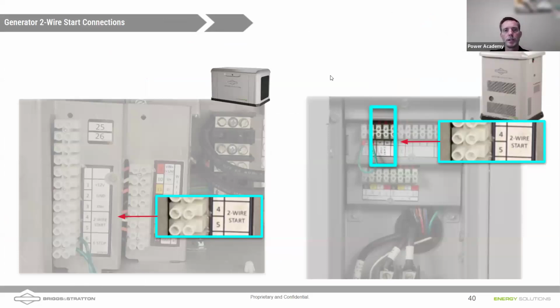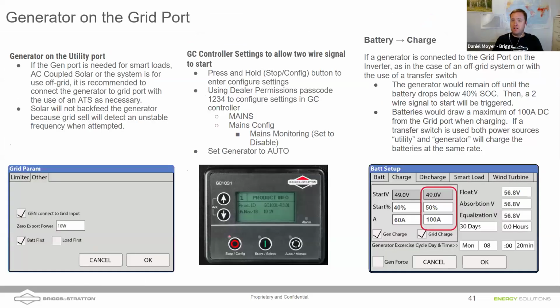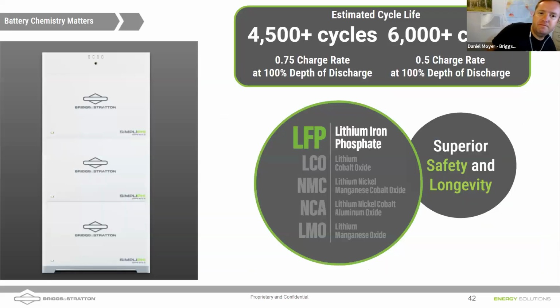What do we also have to do, Daniel, to get the generator to start up? Yeah, I realize we just got a couple minutes left, but one thing you have to do is program the generator so that if it still sees the presence of grid, which it will if you're microgridding your home, it can still start up and listen to that 2-wire signal to start. So by default, that setting is not enabled. So you got to get into the controller and change that as well. Yep, and we give those instructions here. And I understand we're almost out of time.